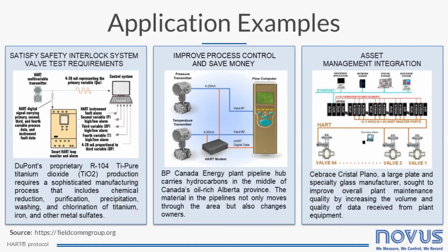BP Canada Energy achieves accuracy between 0.1 and 0.2% in custody transfer of oil as it changes ownership, road to and from sites across Canada's oil-rich Alberta province, to meet contractual requirements. In roughly a decade, a majority of 600 transmitters were upgraded with HART devices and flow computers, handling up to 4 transmitters each. HART communication provided an all-digital data path, eliminating the need for analog to digital conversions, which were resulting in metering inaccuracies. Transmitters were also upgraded for greater accuracy.